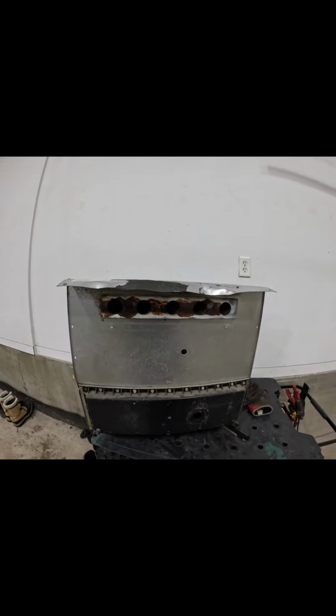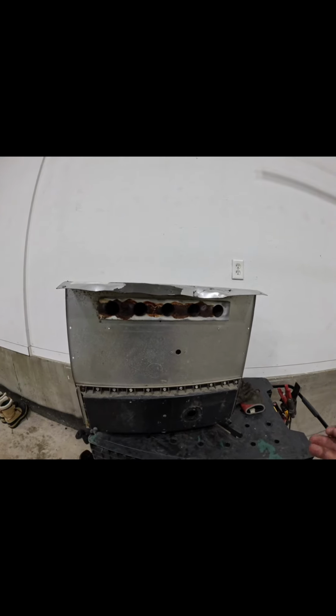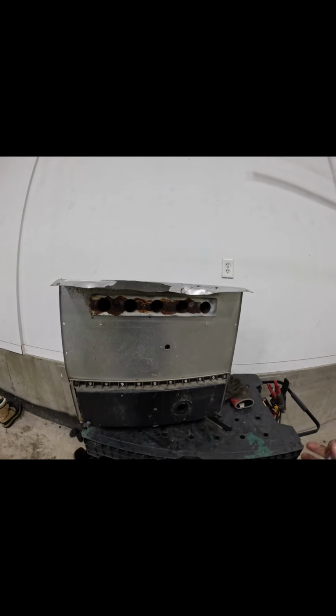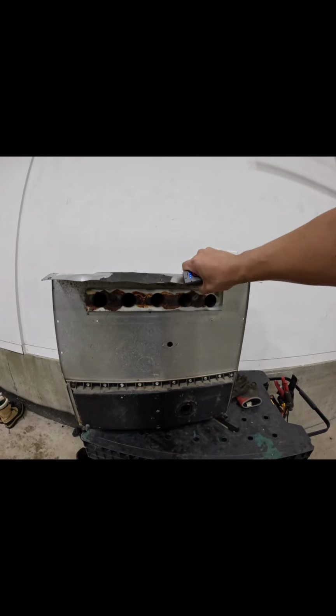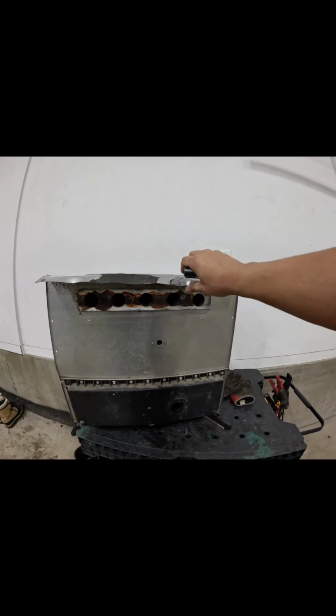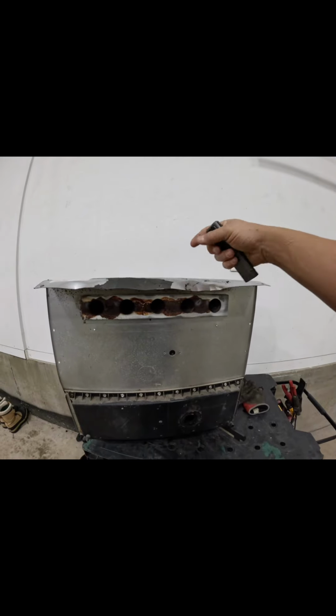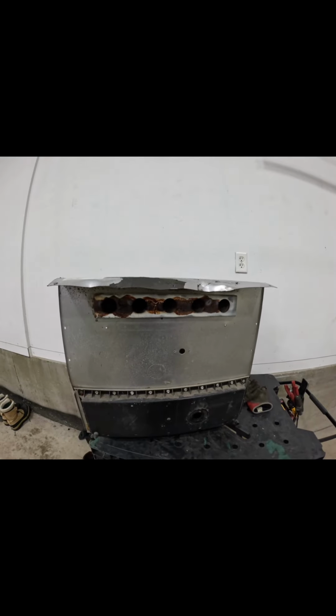Some units are a little different - sometimes you get a 70,000 BTU unit that has 3 tubes, sometimes 4. It's hard to say, but basically what happens here is this got bent in the removal process, so the flame does not go down the tube properly.